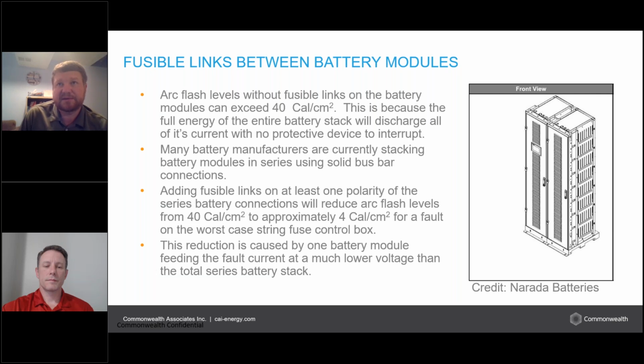And what you'll find too is, since you don't have all those cells behind you, your total system voltage drops significantly. So even though your fault current is high, your system voltage will drop from your DC operating voltage of somewhere between 800 volts and 1500 volts down to the cell voltage, which is typically between 40 and 60 volts. So that greatly improves your arc flash performance.